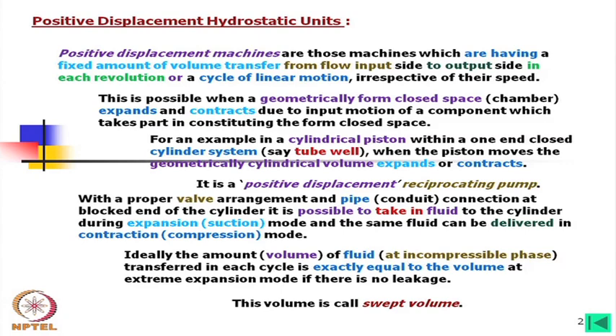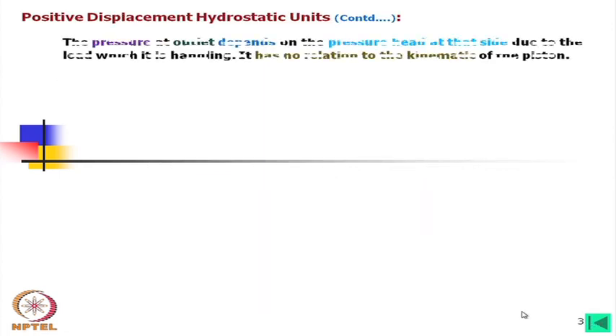In positive displacement machines, the volume is taken in and then cut off; the whole volume is pushed out on the output side. Usually there is no suction head for a positive displacement pump, though depending on the machine it may have a low suction head. The pressure at the outlet depends on the pressure head due to the load being handled, and has no relation to the kinematics of the pistons. If there is no load, only the fluid is being moved with minimal resistance pressure.